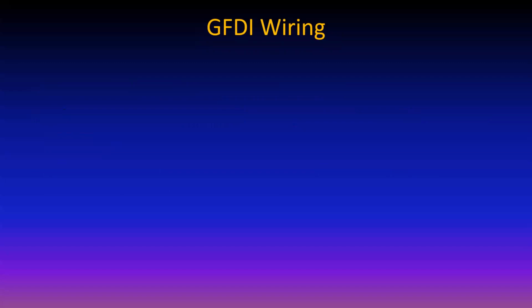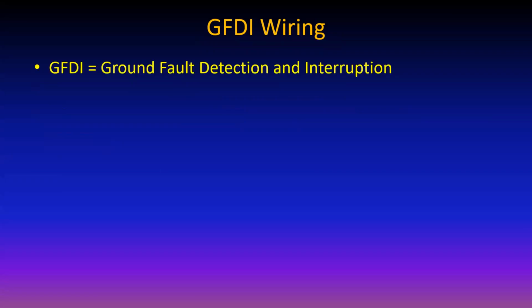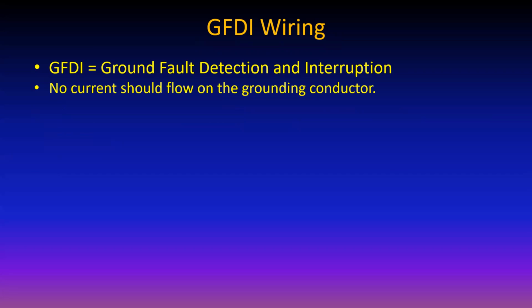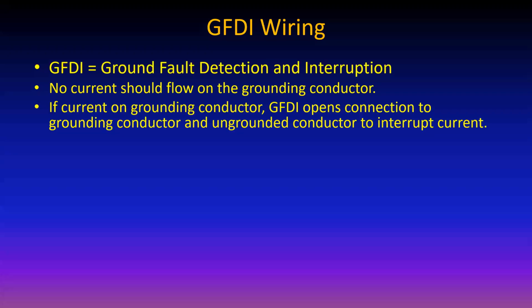And then there's ground fault detection interruption. And mostly, GFDI, by the way, is different from GFCI, ground fault circuit protection, because the GFCI typically trips on 5 milliamps. You put one of those in a PV system, it's going to trip every day. So these trip at a higher current, and they're intended originally for fire and arc fault protection, as well as some protection of personnel. But there's arc fault detection also required for any PV system mounted on a building, and the arc fault detection is supposed to be your fire protection.